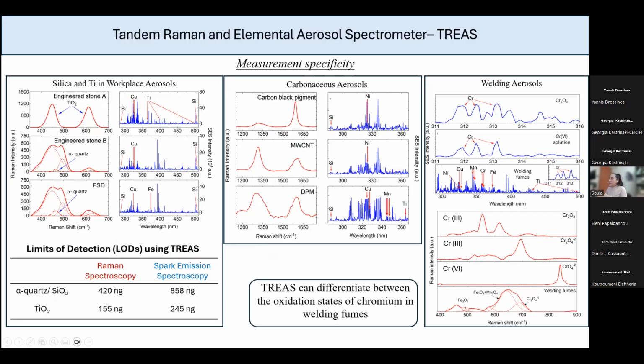So when we have the stainless steel welding fume sample at the last subplot, we want to see what oxidation states we have. We can say with high certainty that it's most likely not chromium 6 because we do not see the peak that we would expect to see, which is at approximately 850. And most likely we have chromium 3, which is probably buried under this peak here that was obtained through deconvolution at approximately 700. So these all show some different applications where this instrument can be used.